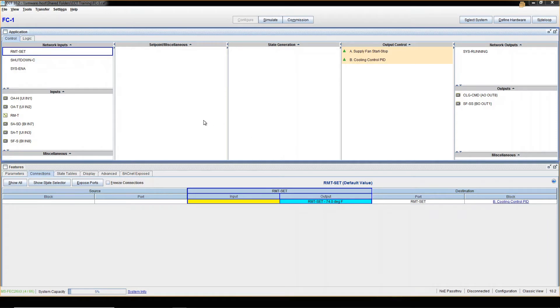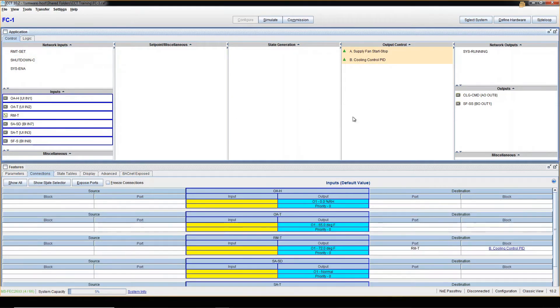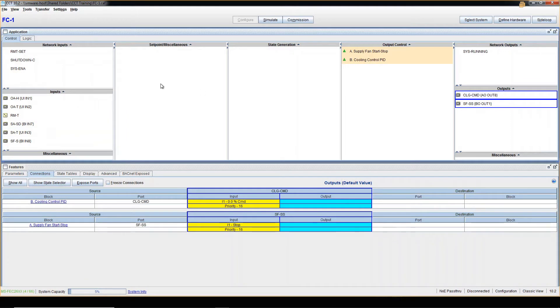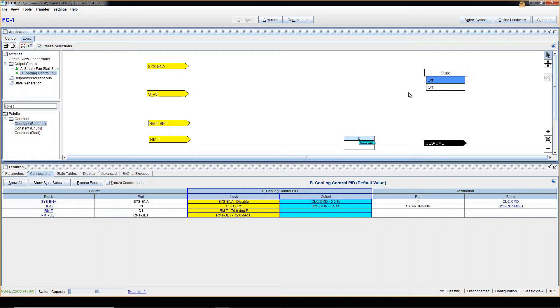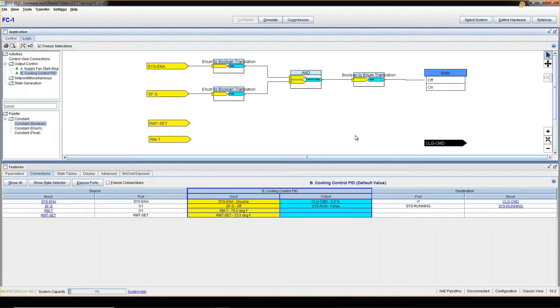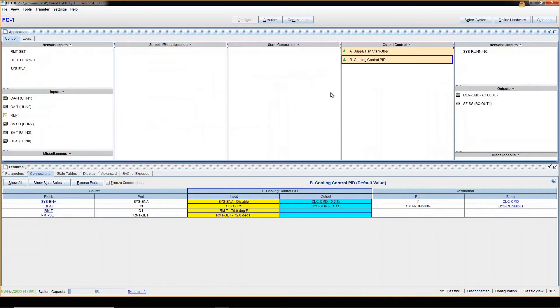Examples of float values would be: airflow 50 CFM (cubic feet per minute), static pressure 2.31 inches per water column, or temperature 7.5 degrees Fahrenheit. Coming back to CCT — when I was talking about inputs and outputs, I was not only referring to the physical controller's inputs and outputs, but to all types: network inputs, network outputs, logical block inputs and outputs, and even inside the logic every single block has its yellow inputs and blue outputs.